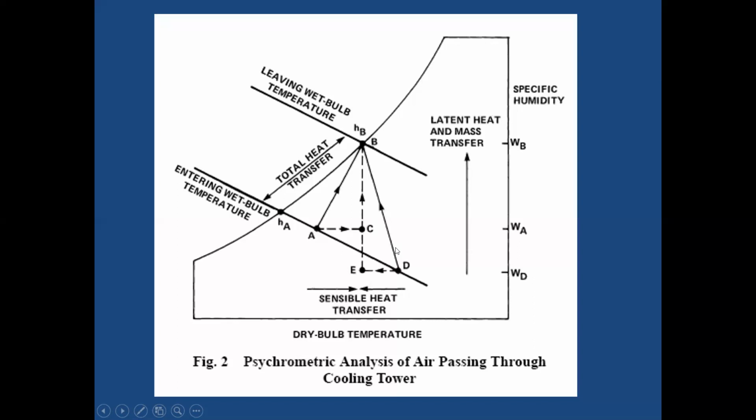So under dry climate, the advantage is that the cooling tower range increases, but at the cost of more water vapors, meaning more makeup water. On the other side, in the humid climate, the cooling tower requires less makeup water, but at the cost of low range. So we have to compromise. Depending upon the conditions or the load, the cooling tower is preferred.